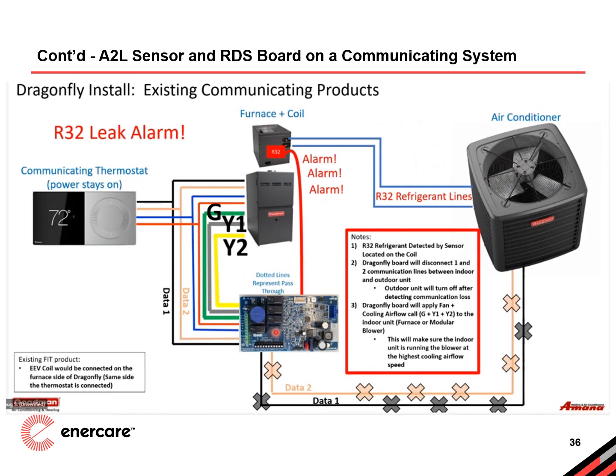But what happens when the RDS board detects a refrigerant leak in a system with a communicating thermostat? As soon as the A2L sensor picks up a leak, the Dragonfly board steps in to take control. And here's what happens next. First, the Dragonfly board disconnects the communication lines to isolate the indoor and outdoor units, effectively shutting down the outdoor unit immediately. Secondly, it applies a cooling airflow call at the indoor unit. This forces the blower to ramp up to cooling speed to help disperse any leaked refrigerant safely and maintain airflow by powering the G, Y1, and Y2 circuits at the furnace.